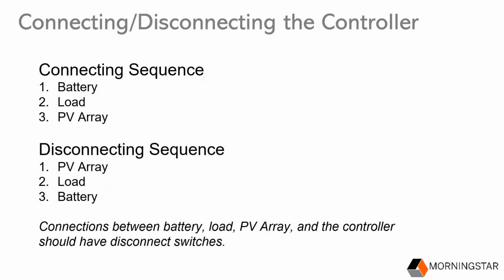When installing a controller, this is very important. You want to connect the battery to the controller first, then you want to connect the load to the controller, and lastly, you connect the PV array. And when disconnecting, you just reverse that order. The battery provides power to the controller, so you always want to make sure that the solar and loads are disconnected before connecting or disconnecting the battery from the controller. And this, of course, applies to all Morningstar controllers.